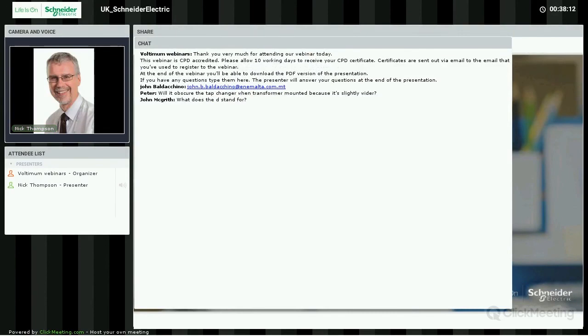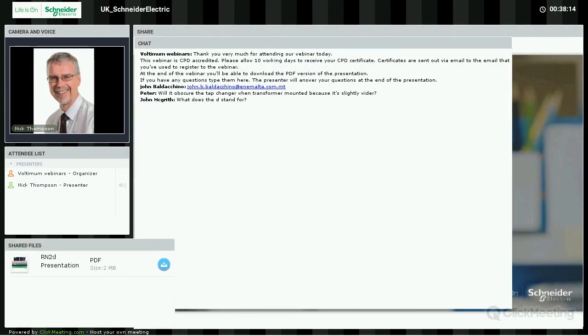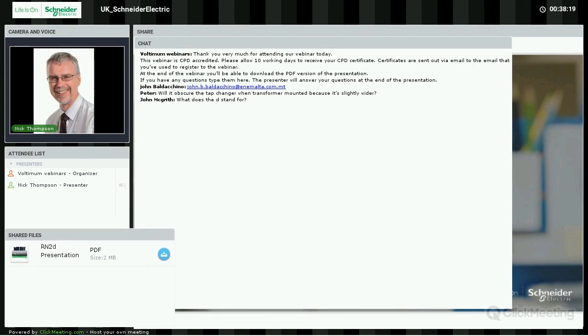The first one is from Peter. It's very much a unit which is like the RN2C, and it won't actually interfere with the tap changer when you've got it mounted in a unit substation. We've looked at that very, very carefully. Even though it's slightly wider with the cable boxes, we've been mindful that we can't obscure the tap changer when you need to either set it up or make any changes. So I hope that satisfies the question.